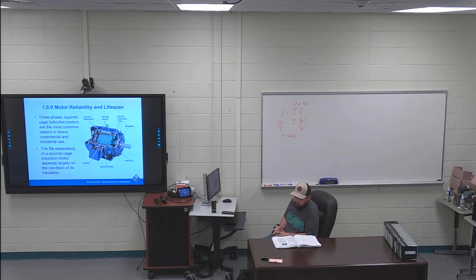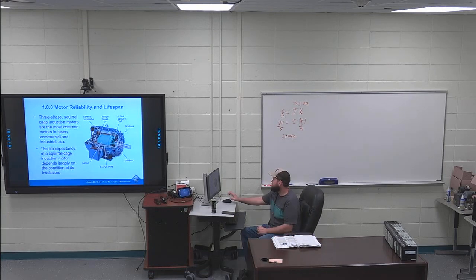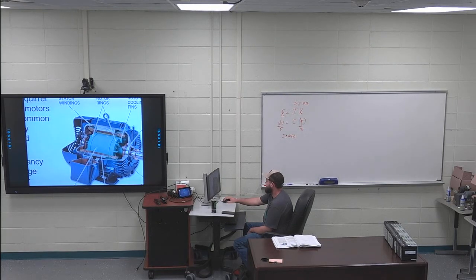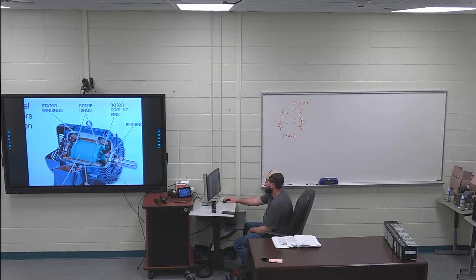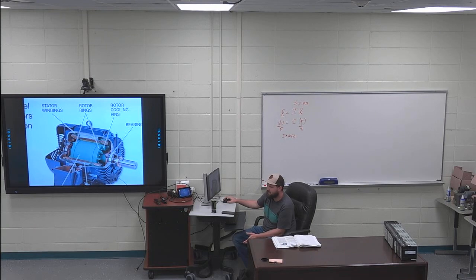But my first highlight on page 1 is the second sentence on the page. The life expectancy of a squirrel cage induction motor depends largely on the condition of its insulation, which should be suitable for the operating requirements along with the performance of any required maintenance. If you're looking at this motor right here, you can actually see your stator windings in here, and it looks like just a bunch of copper. This is not just a bunch of copper. They are copper windings, which are insulated from each other with a glass-like insulation. It's not glass-like, but it's clear.